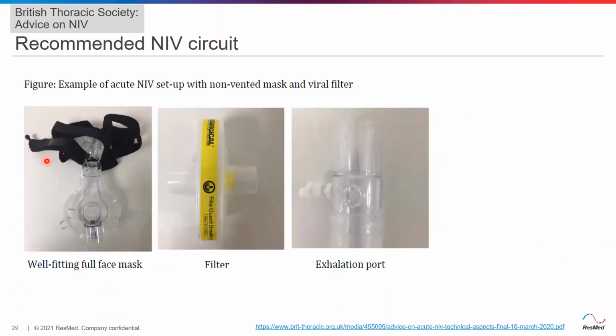First is the full face, well-fitting full face mask. Ideally, this mask should be a non-vented mask. For a non-vented mask, the elbow should be blue. Although I have taken this picture directly from the BTS advice, they should be blue. Ideally, they should be a well-fitting full face non-vented mask. Then a filter, to which this mask would be connected, and an exhalation port. On the other end, this exhalation port would be connected.